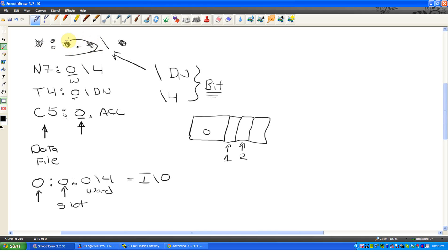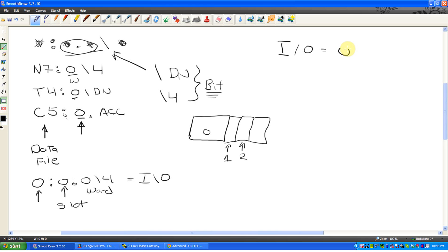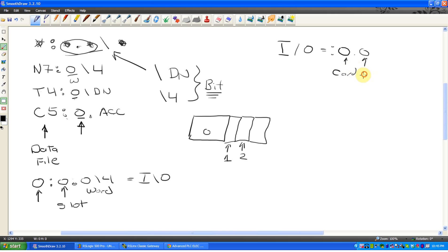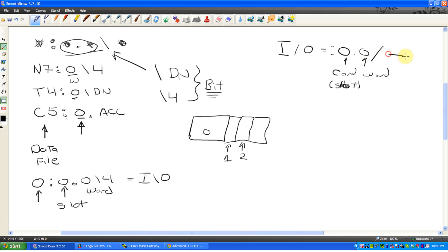This can be a bit confusing, and maybe over here to simplify it a bit more. If it's IO, so if it's an actual input or output, after the colon, you're going to have, so it'd be colon zero dot zero. It's which card is it on? Which word? Card word. This card is quite often referred to as the slot. As the slot number. So card, word, and then obviously slash what bit on, what bit in this word on this card.